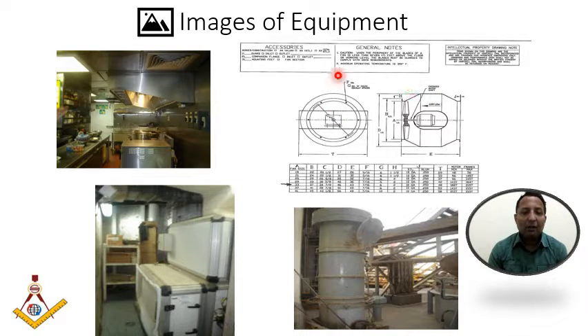This is a fan with a motor, and the motor is a bifurcated type, meaning it's not exposed to the airstream or exhaust coming from the kitchen. The reason is simple: the exhaust airflow from the kitchen contains grease or oily fumes which may deposit on the motor body, and oil being hazardous and fire-friendly material, it's not advisable for it to deposit on the motor.